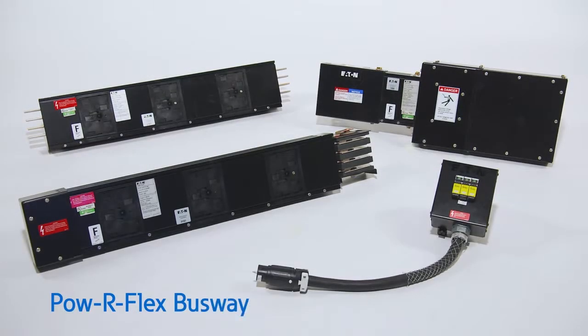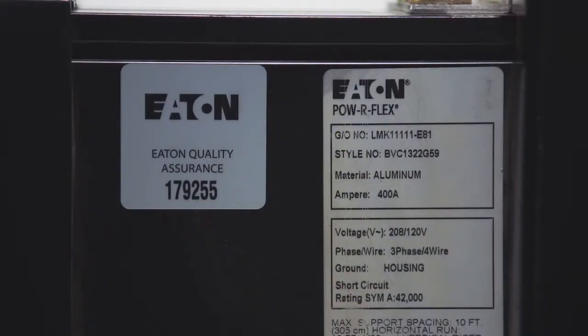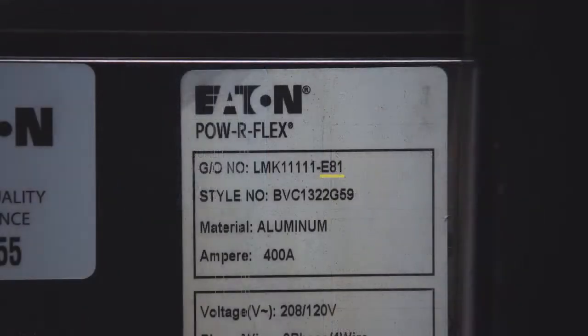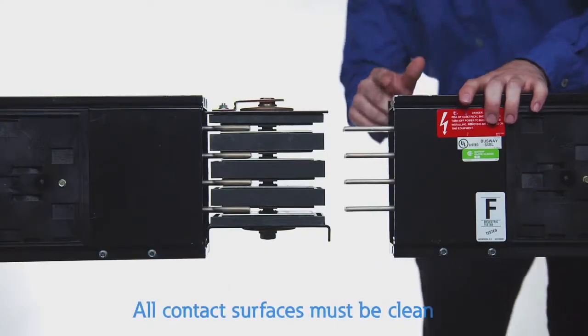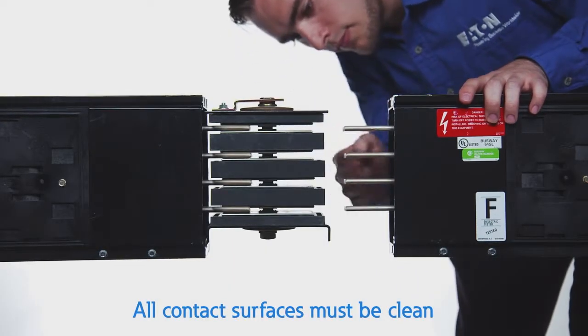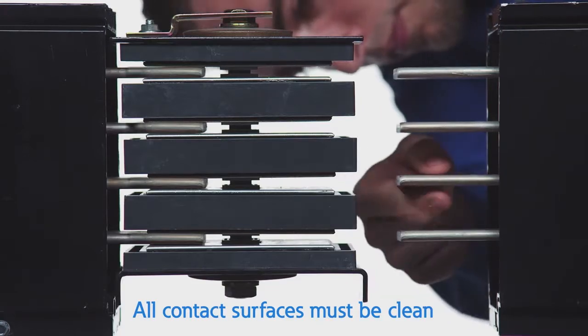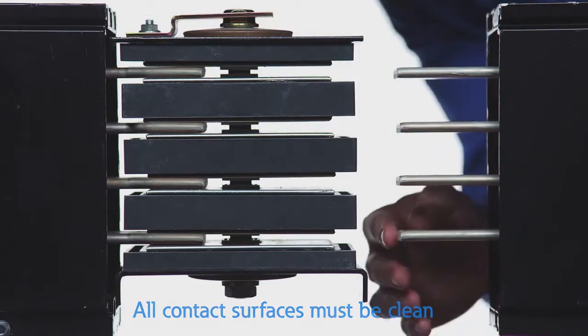This video will give you a step-by-step guide for installing the EATON Pow-R-Flex low ampere busway. Each piece has a label which identifies the piece and its ratings. At the end of the GO number, there is an item number, which looks like this. It corresponds to the item number on the construction layout drawings. Before you connect the pieces, make sure all contact surfaces are clean and free from contaminants.